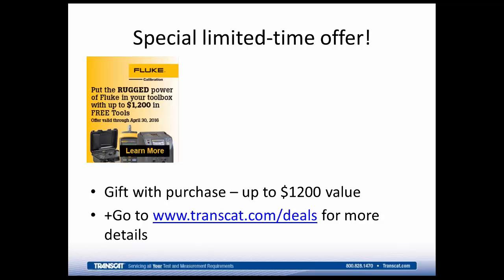Okay, last question. What should the accuracy of the reference instrument be in comparison to the test instrument? Okay, so that is a very wide open question as well. So normal calibration, you've got a device that you're testing, and you've got some device that's more accurate than it that is your reference. And the question is, well, how much more accurate does it need to be? There's not a proper answer I can give in 30 seconds or less.